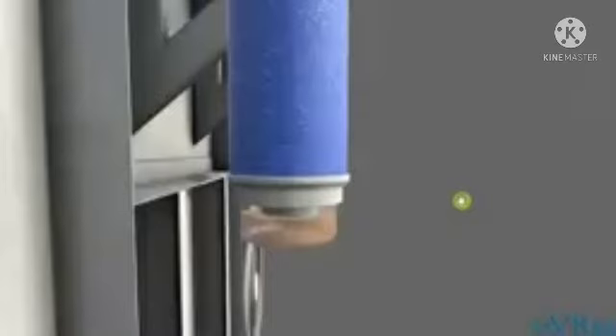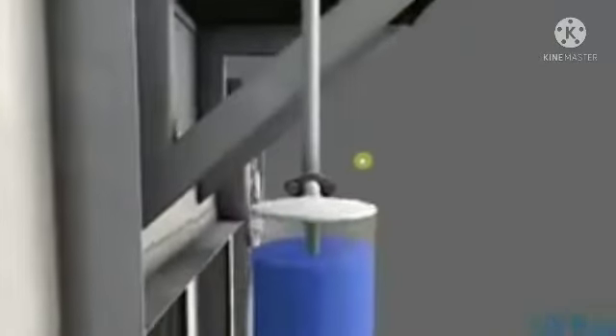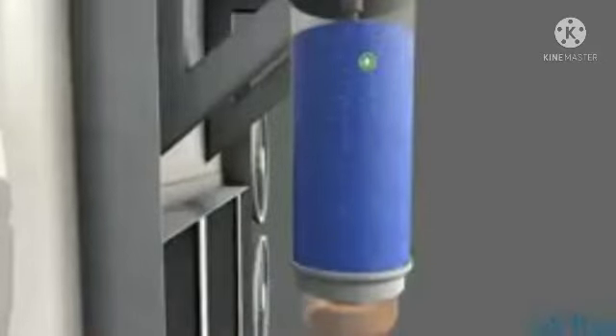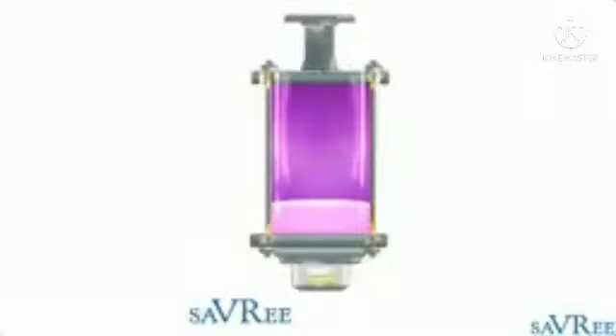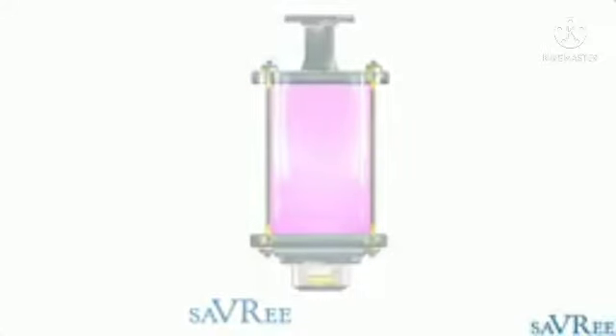This may lead to a buildup of sludge when the moisture comes into contact with oxygen. Not only that, but the dielectric strength of our insulating liquid is going to be reduced. So these are all negative effects. So what we'll do, we will pass the air through a silica gel breather. That is this item here. It's full of silica gel beads. And the silica gel beads will remove the moisture from the air. As they remove the moisture, they're going to change colour. And when the colour has changed by 3/4, we know it's time to change the silica gel beads. So the colour change is purely for a visual indicator to see how saturated the silica gel beads are. Once the air has been dried, it's going to pass into our conservator tank.